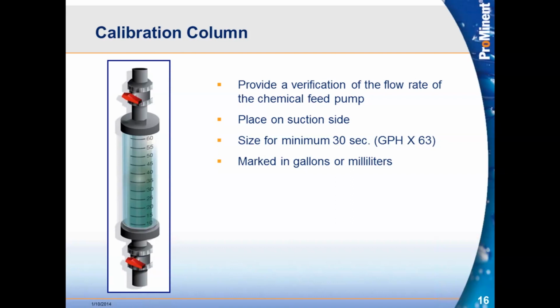So to do that routine, we want to know a true volume number. So we want that calibration column. We're going to pay attention typically to the milliliters in graduation on that calibration column. I put a little note to the right there where we're sizing it for 30 seconds. Gallons per hour, if you take what the pump is rated for in gallons per hour and you multiply by 63, it's the magic number, 63, that's going to give you the milliliters in a minute. Okay, so gallons per hour times 63 would be milliliters per minute. 63 is, there's 3,785 milliliters in a gallon, and if we divide that by 60, I think we should be pretty close to that 63 number. So that's where that 63 comes from. But gallons per hour times 63 will give you milliliters in a minute.